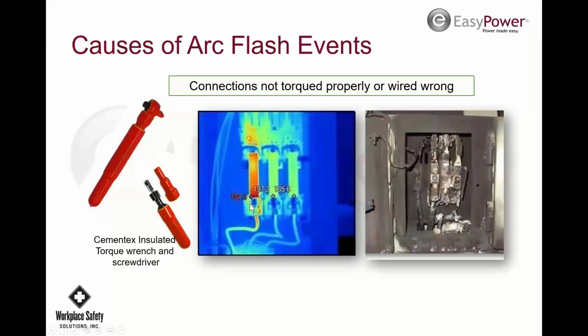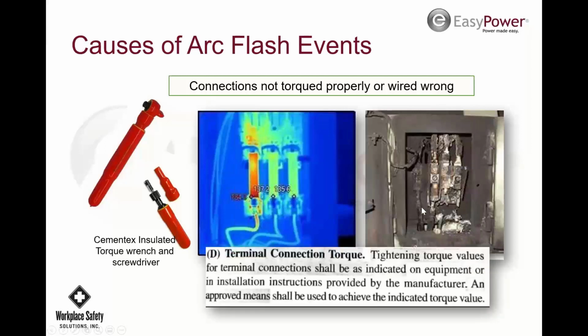They're required. Also, a new requirement is that manufacturers have to put the torque setting on the terminal itself, not just on the box of terminals. So this is the result if you don't pick it up with an infrared test and you let it go. Then this ends up happening, and of course you have an outage, maybe damages. This is the NEC requirements for tightening and torquing your equipment.